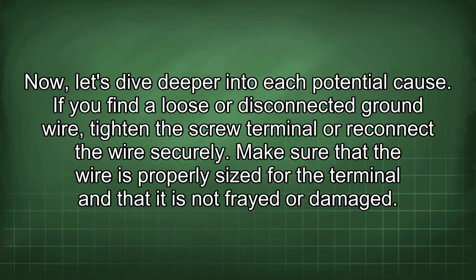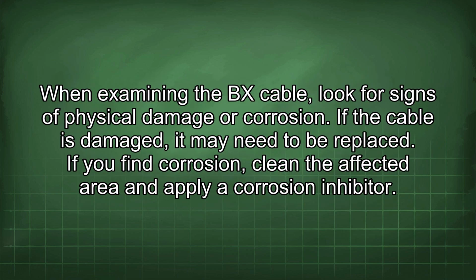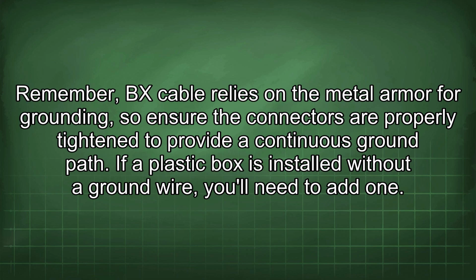If you find a loose or disconnected ground wire, tighten the screw terminal or reconnect the wire securely. Make sure that the wire is properly sized for the terminal and that it is not frayed or damaged. When examining the BX cable, look for signs of physical damage or corrosion. If the cable is damaged, it may need to be replaced. If you find corrosion, clean the affected area and apply a corrosion inhibitor. Remember, BX cable relies on the metal armor for grounding, so ensure the connectors are properly tightened to provide a continuous ground path. If a plastic box is installed without a ground wire, you'll need to add one.